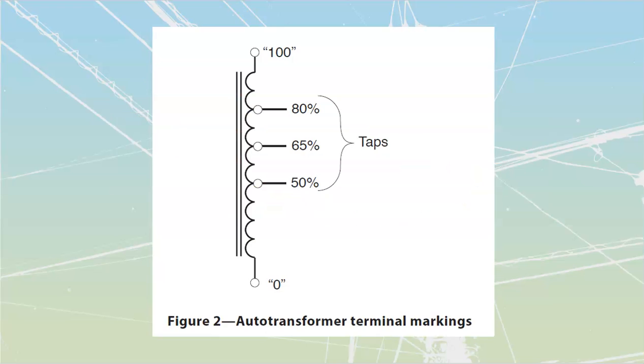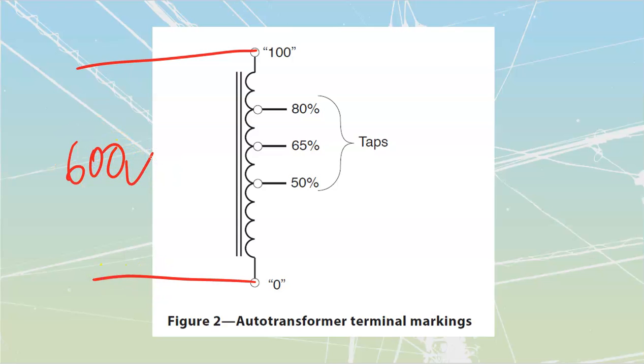Autotransformers themselves you should be familiar with from your second year. Basically, it's a transformer which shares its 100% winding along with a partial winding, where some is directly transmitted out to a load and some is brought in over here. I could feed 600 volts into my 100% taps over here. Then I would be able to take a smaller amount of voltage off any of these. I'd be able to take 300 volts off over here, or I'd be able to take off 65% of 600, whatever that would be, 80%, etc. And I can get a smaller value of volts out.